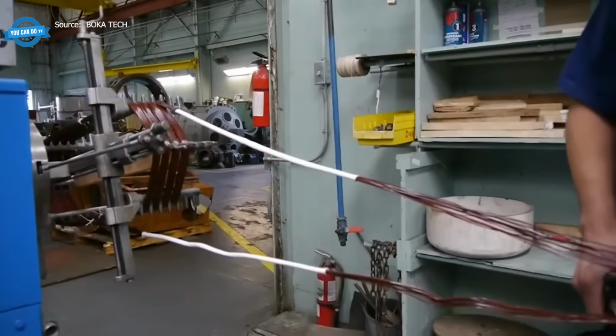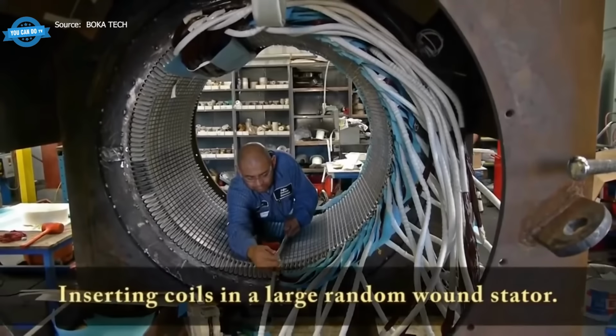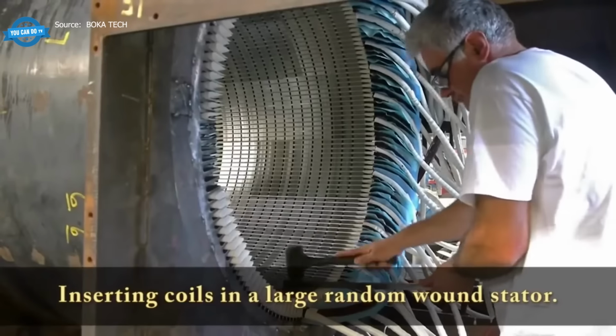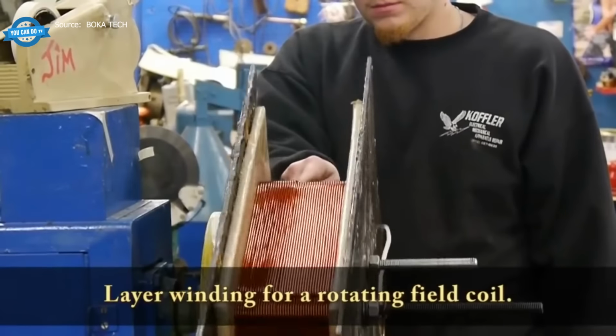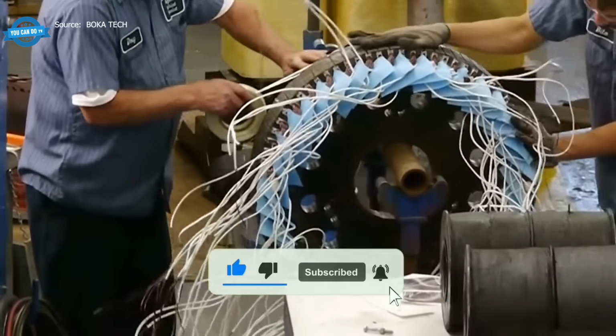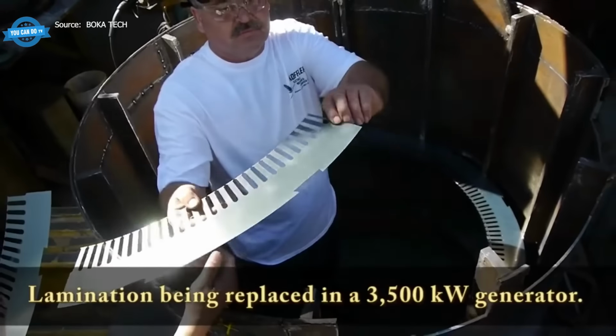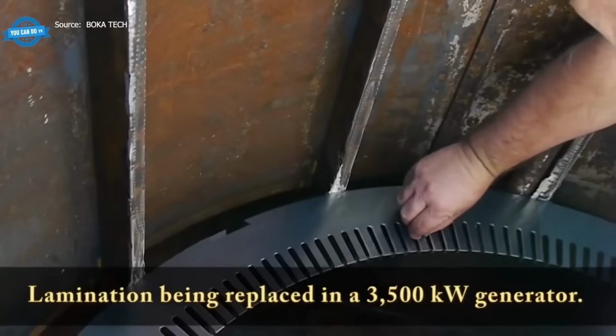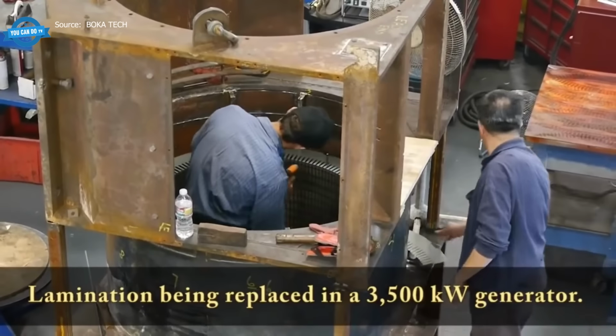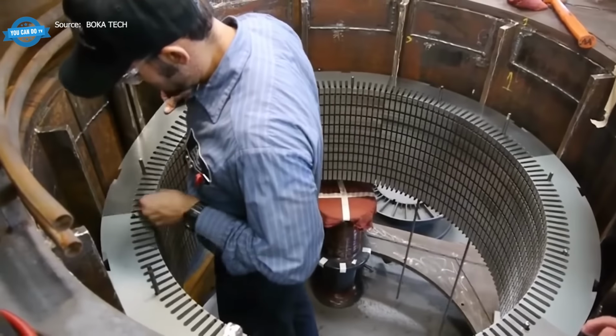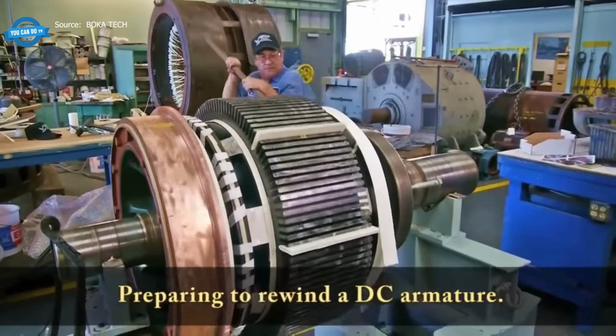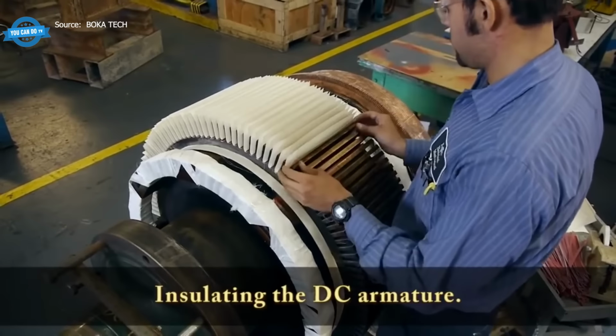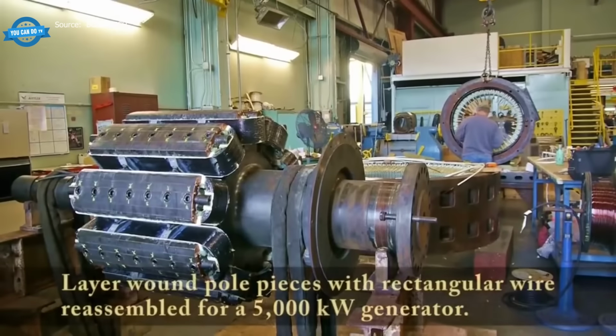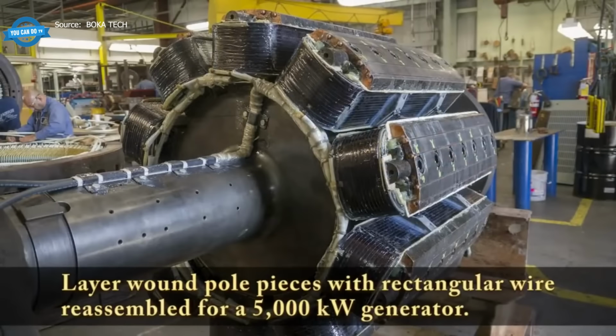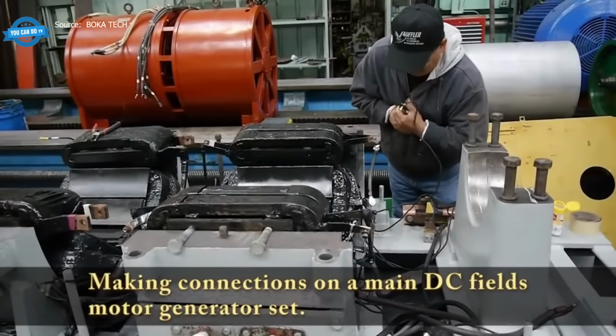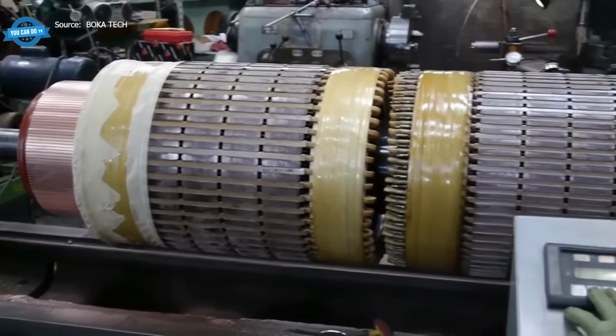Inside every electric motor, the winding pattern is where power density and reliability are determined, and no two winding types are interchangeable. A large motor facility runs several winding processes in parallel across different production lines. Random winding of multi-strand stator coils fills the slot with continuously laid conductors, maximizing copper fill factor. Layer winding for rotating field coils places conductors in precise layers where magnetic geometry requires exact positioning. Exciter rotor winding drives a small generator whose output feeds the main rotor field, removing brush contacts in synchronous machines. DC armature rewinding removes old winding from the armature, prepares commutator segments, and re-insulates each slot.